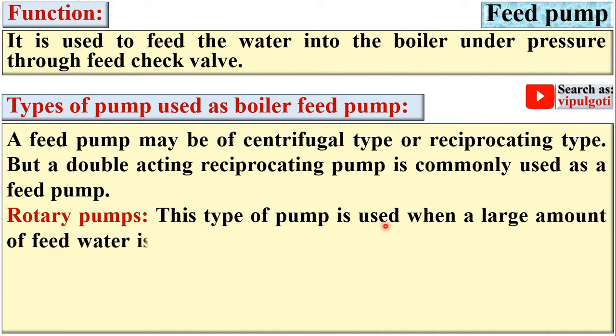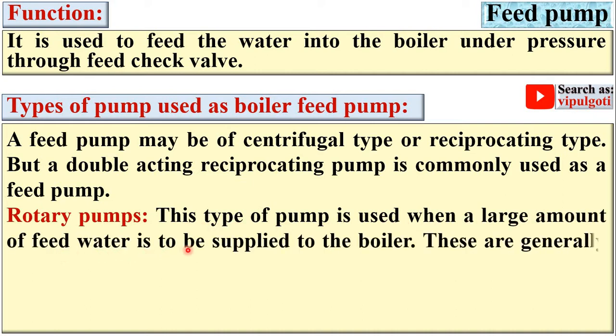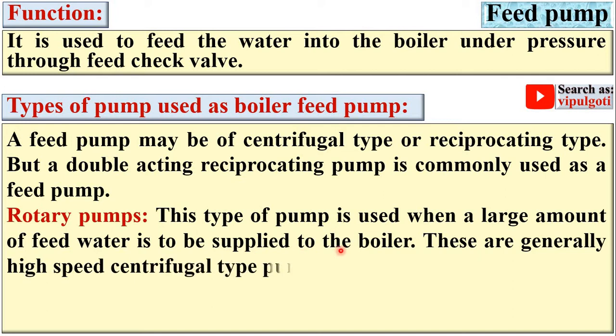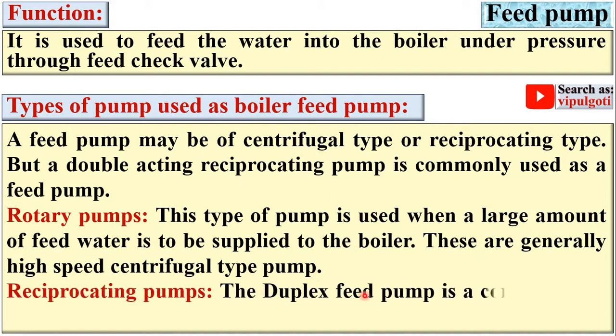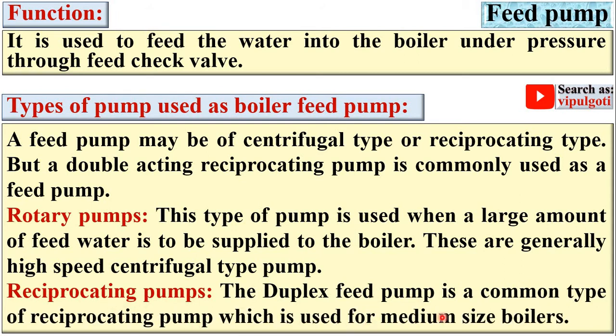Rotary pumps are used when a large amount of feed water is to be supplied to the boiler — these are generally high-speed centrifugal type pumps. The duplex feed pump is a common type of reciprocating pump used for medium size boilers. In short, rotary pumps are for large size boilers supplying large amounts of feed water, whereas reciprocating pumps are suitable for medium size boilers.